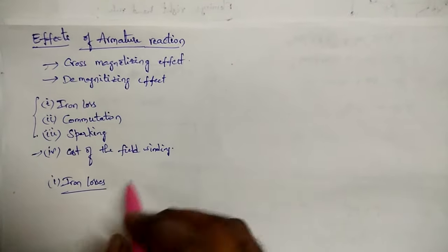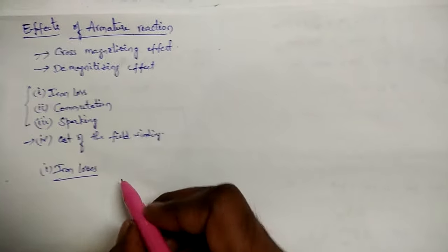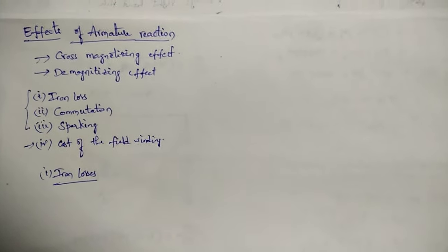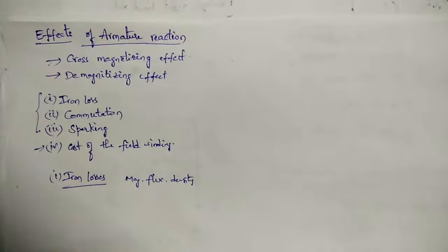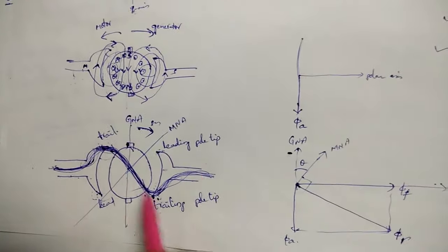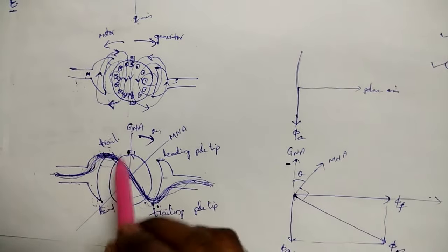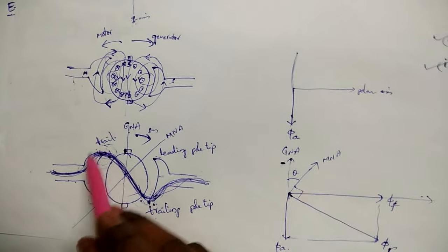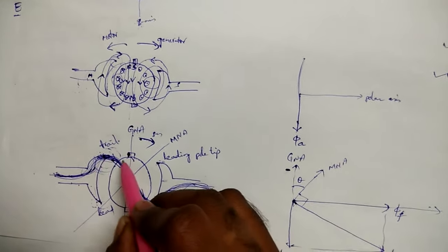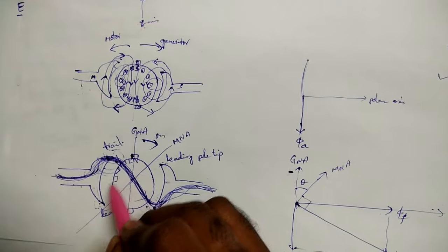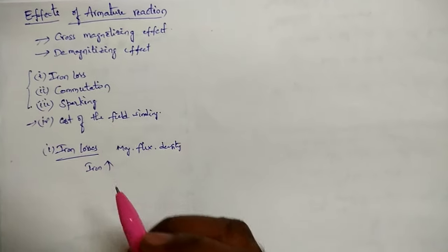Iron losses depend on the magnetic flux density in the teeth and pole shoes — it depends on flux density, not the flux itself. Because of the cross-magnetizing effect, the main field flux is distorted, so in some regions the flux density will be more. Because of this increased flux density in the pole shoes and teeth, the iron losses will be increased.